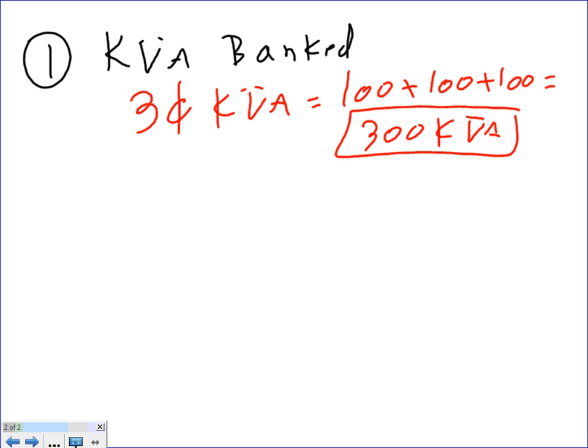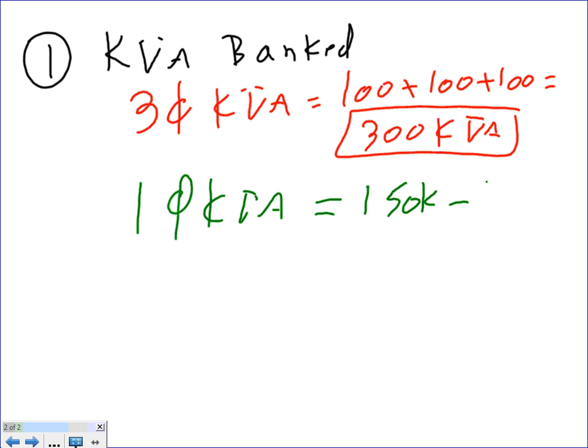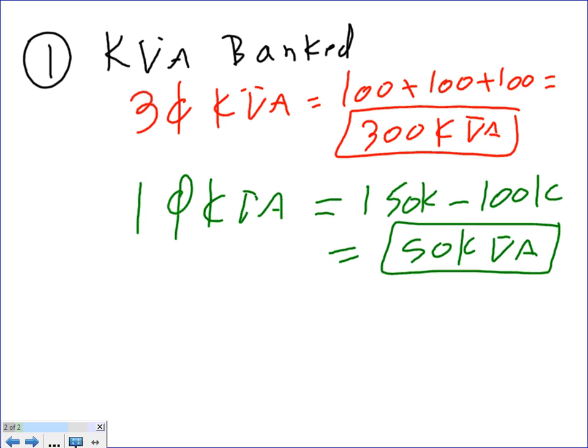What happened to the other 50? The other 50 is consumed by the low volt, by the line to neutral, the single phase. So what's the single phase kVA of the system, guys? 150, thank you. How do you find this one? You take the 100K minus 100K, and that gets you 50 kVA. That's all you have to do.